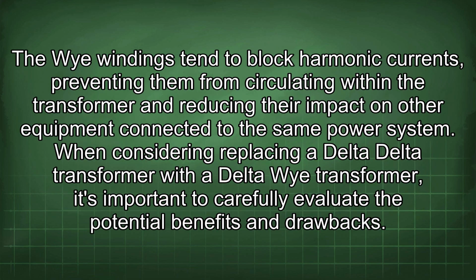The Y windings tend to block harmonic currents, preventing them from circulating within the transformer and reducing their impact on other equipment connected to the same power system. When considering replacing a delta-delta transformer with a delta-Y transformer, it's important to carefully evaluate the potential benefits and drawbacks.